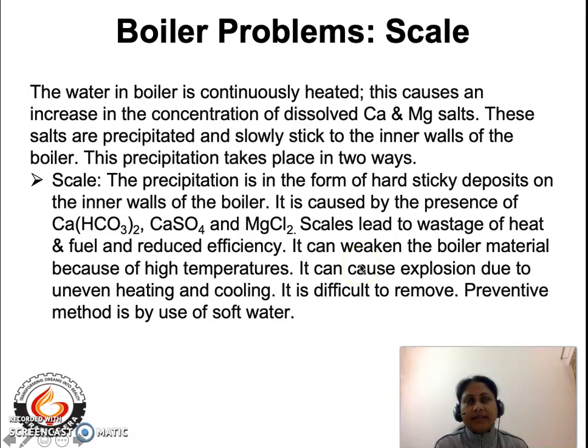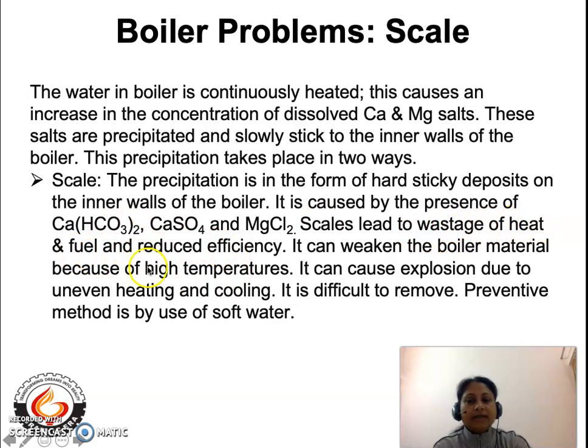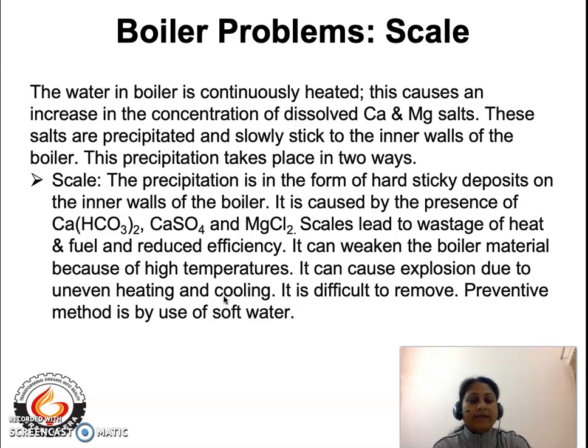Scales create several serious problems inside the boiler. First, they lead to wastage of heat and fuel because scales are bad conductors of heat, reducing the efficiency of the boiler. Second, scales can weaken the boiler material due to high temperatures. Third, scales can result in explosion due to uneven heating and cooling, which can lead to the death of operators working near the boilers.